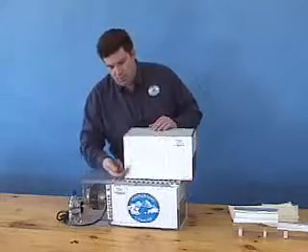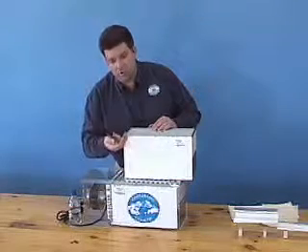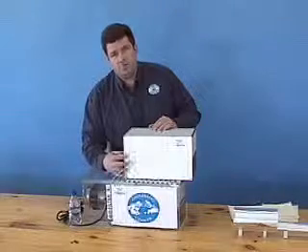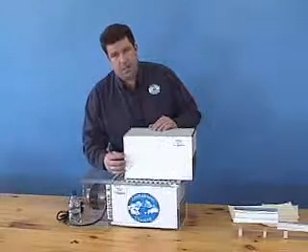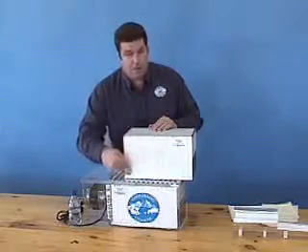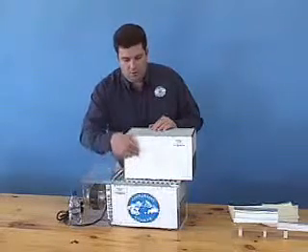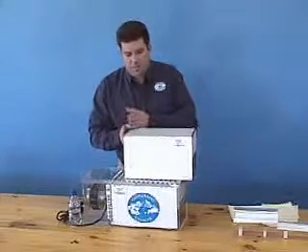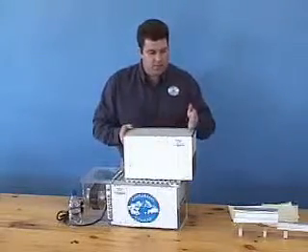As the first 1/13 of air travels in cross flow to both the working and product air, it takes heat away from the dry channels from the plastic heat exchanger. This same process occurs another 12 times, incrementally cooling both the product and working air streams as the air travels down the heat and mass exchanger.